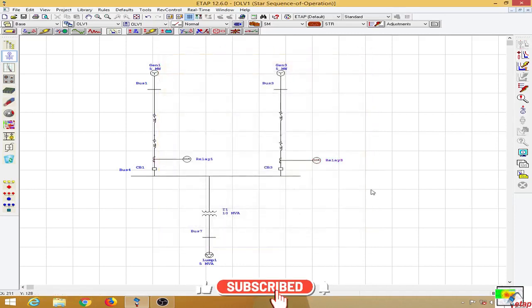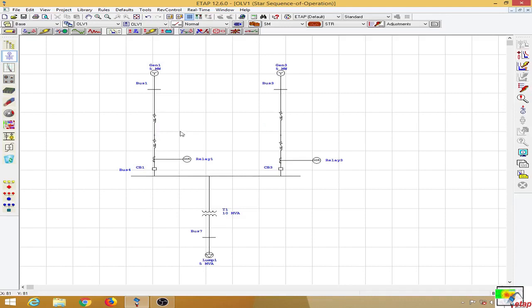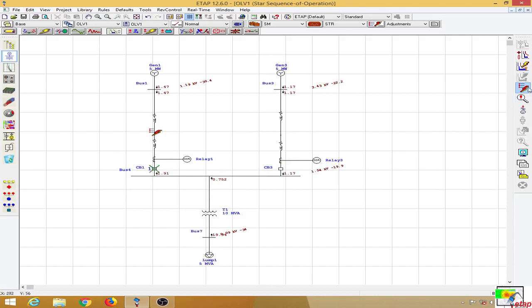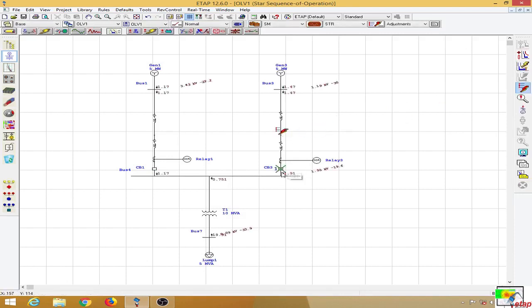Now let us see how we can discriminate between faults on the two lines. I apply a fault at this point, and you can see that only this circuit breaker has operated because the current is flowing away from the bus. When this portion is isolated, the other source can continue to feed the load. Testing on the other line as well — you can see that only that circuit breaker has operated, and the other has not.